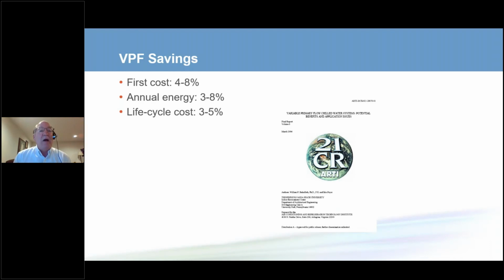Bill Bonfleth, who's an ASHRAE presidential member, and a research student of his, Eric Pyre, did research comparing systems that were originally designed using the old flow rates and changed to the ASHRAE, or used primary secondary systems and changed to variable primary flow systems. And they found that the first cost goes down because we don't have 2 sets of pumps. We don't need the space for the pumps. We don't need all the piping connections for those pumps. And the annual energy cost goes down. So like reducing the flow rates and increasing the delta T's, we can reduce both the install costs and the operating costs. And they published that in a paper.